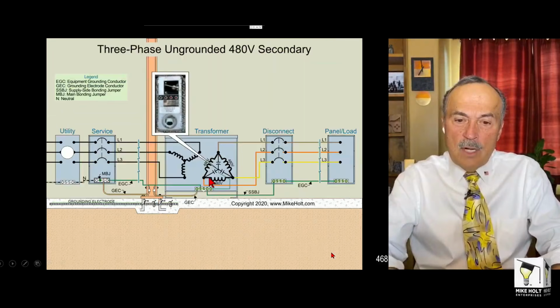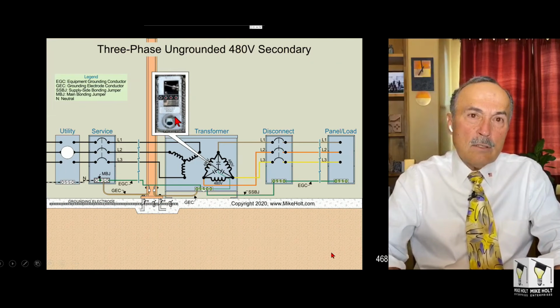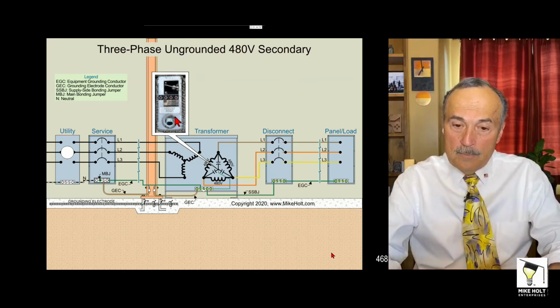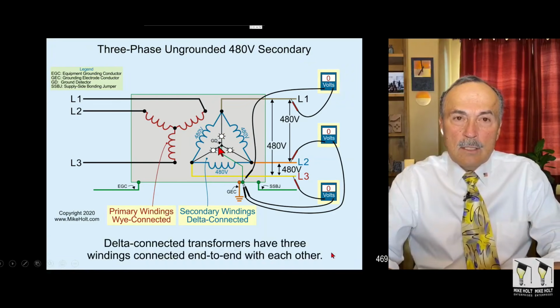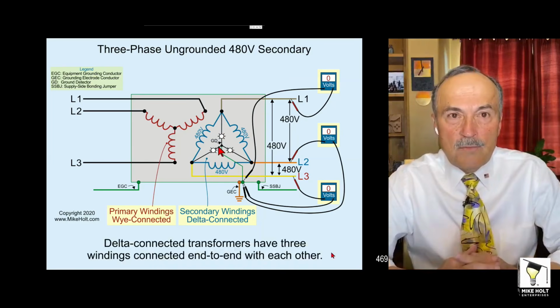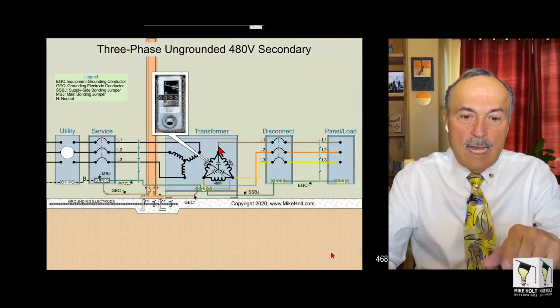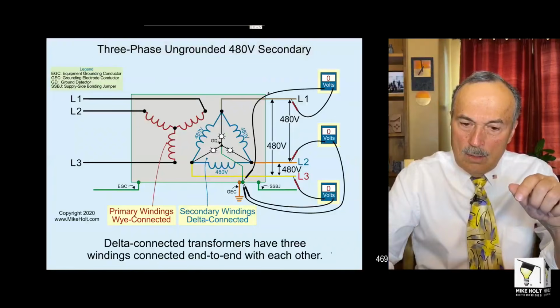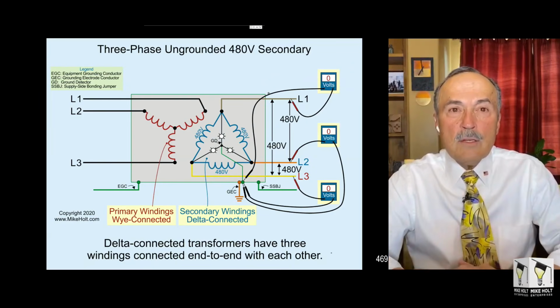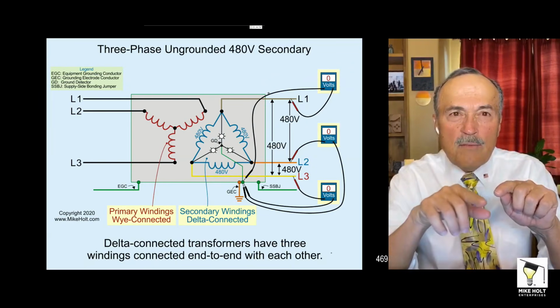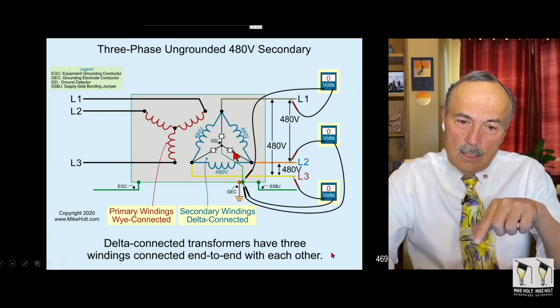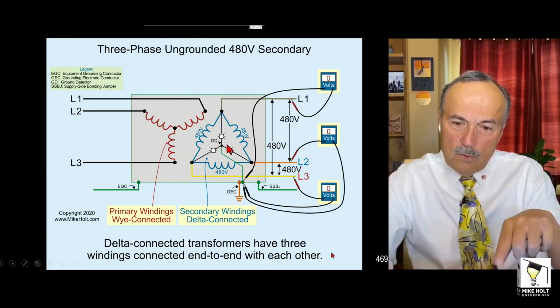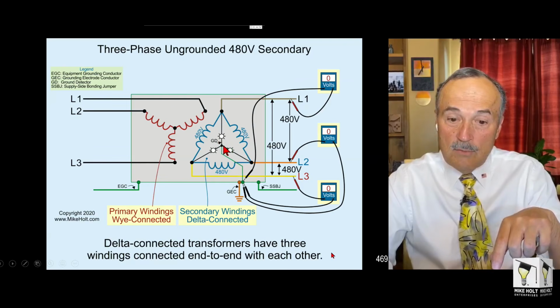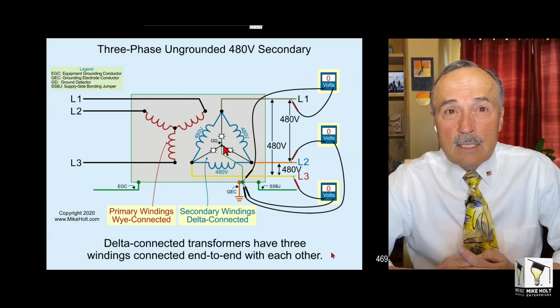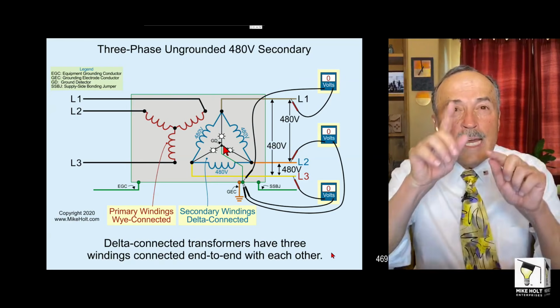So what does it look like? Well, if you have an ungrounded system, you're going to have a ground detector so they can know that something happened. We talked yesterday about the lights; back in the 40s and 50s, they used lights. Today they use ground detection systems. You can see something like that, okay? Years ago it had lights, the way they were configured. And the lights were, I think, 575 volt lights. 277 would be, I don't know what the voltage is with the ground here. But what it was is less than 575. So the lights were dim.